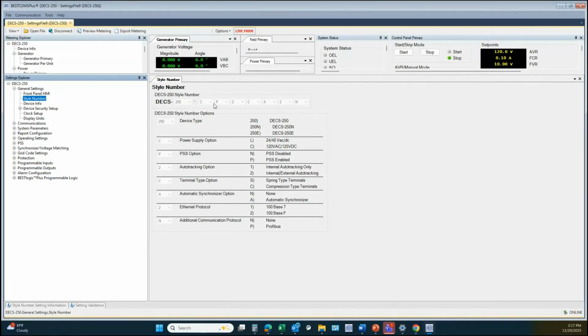You can see here on my screen that the options are all grayed out, and that is because I am communicating with the unit. One thing I failed to mention that's important to note: whenever you are communicating with a unit, the software will state in the bottom right hand corner that it is online. It is possible to have multiple plugins of the software open, and one of them would be communicating with your unit and the other would not be. And in that scenario, if you're making changes to the one that's not communicating, those changes are not going to get saved to the unit, obviously.